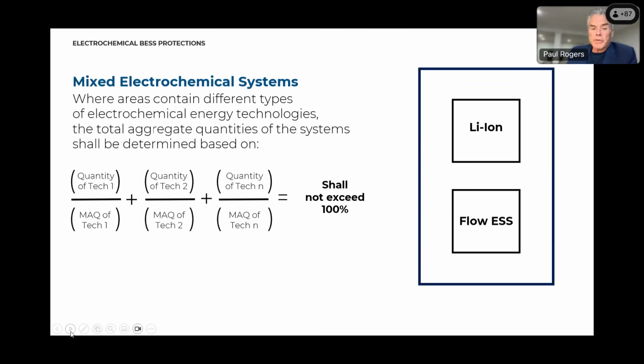We don't see this often, but there is a section where if you had a lithium-ion and some other chemistry associated in the same particular area or room, you have to go through and take a look at the aggregate amount, do this total aggregate, and show that if there was a fire on each one of them, whether a flow battery or lithium-ion, it would not have adverse effects on the adjoining ones, whether fire or any other type of leakage in some cases, that it would not affect the adjoining chemistry in that area. This should be done as part of the hazard mitigation analysis too. So we can move on to the next slide.